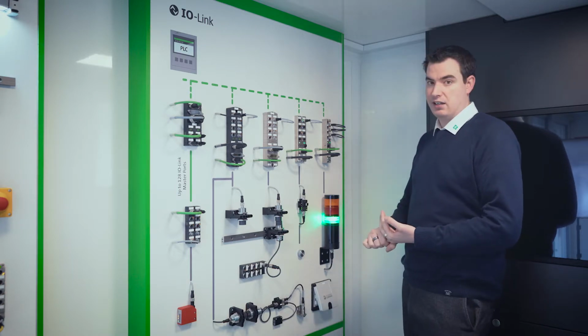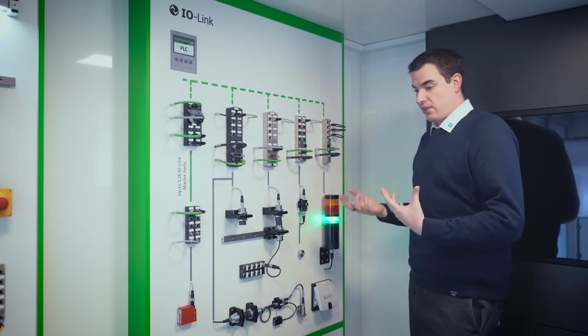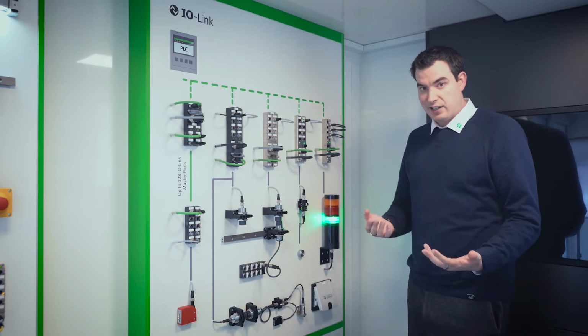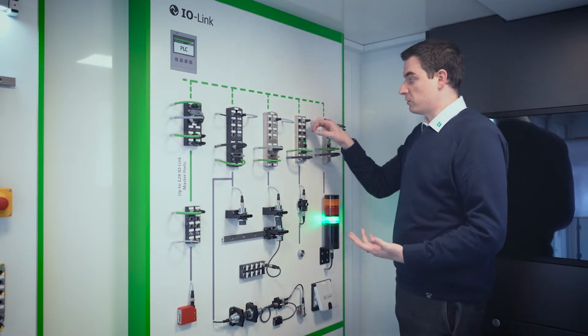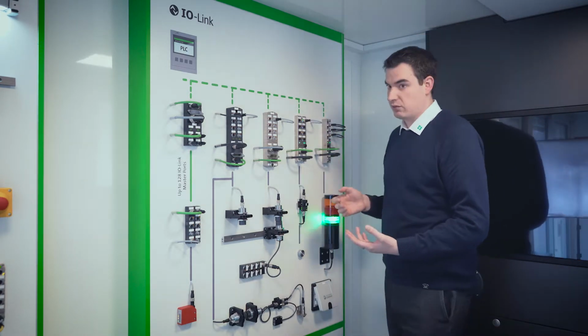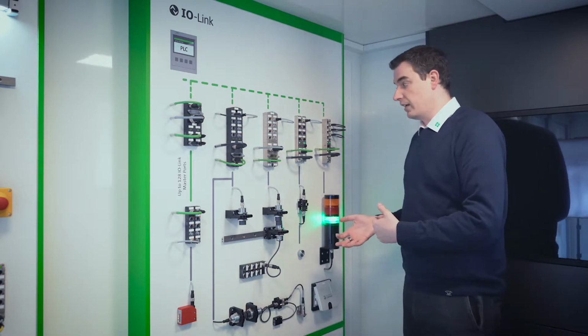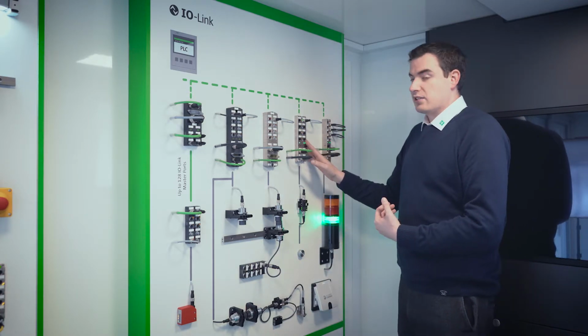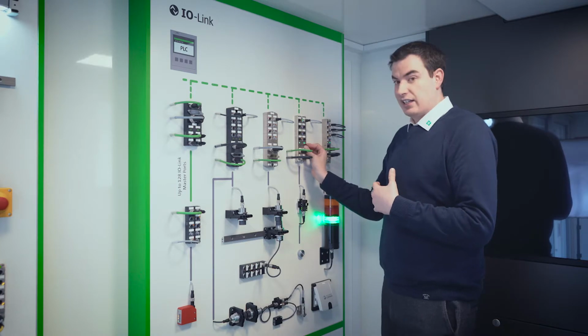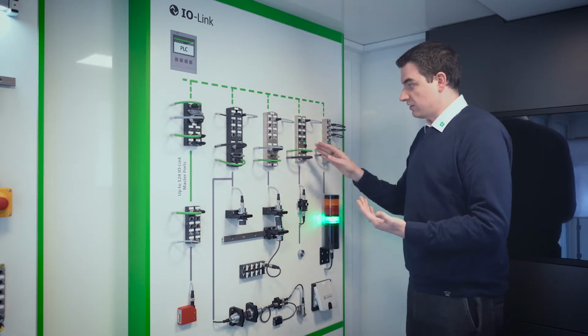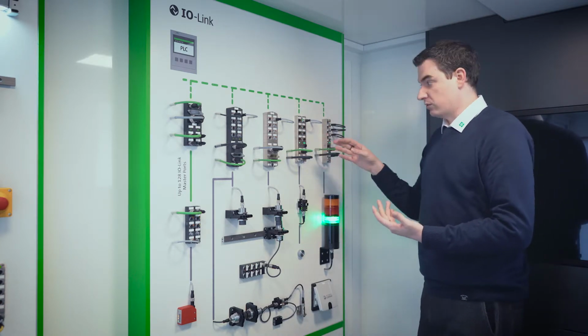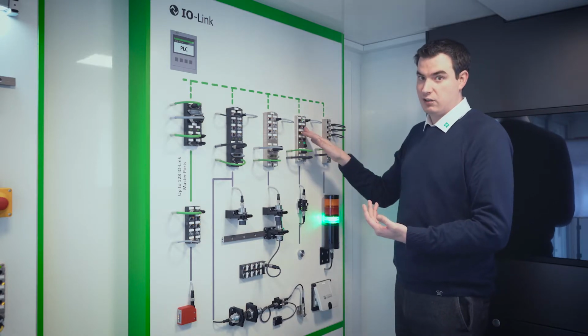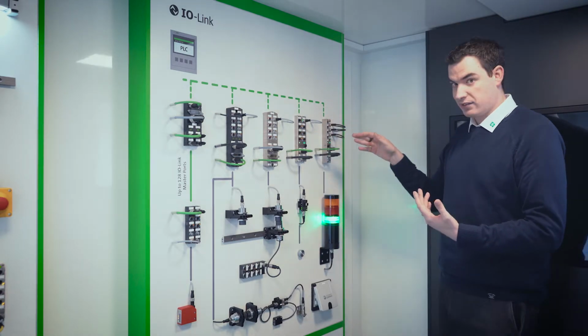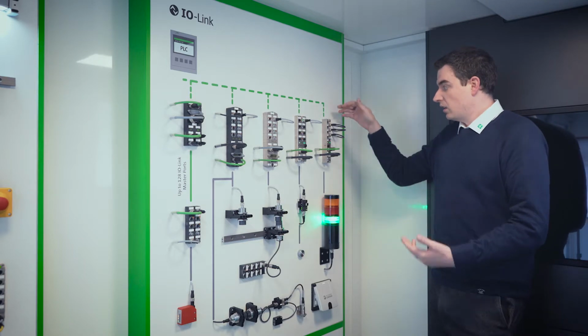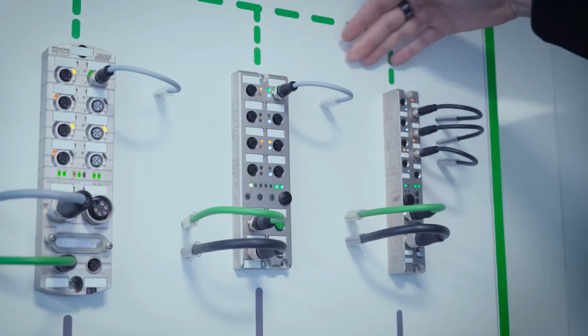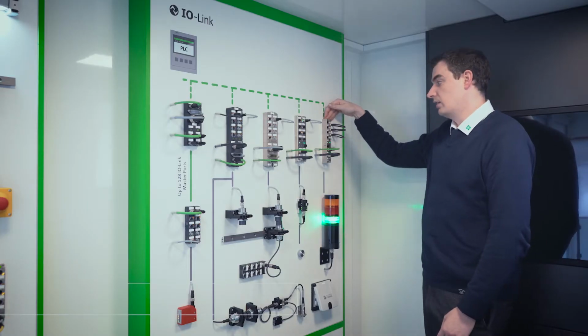the outputs and the IO Link, rather than waiting for the software engineer to get to site before they found that actually some of the points may have been wired incorrectly, or done to the wrong part in the software. Using the web server interface, the installation engineers on site can connect to this and view the actual data, not just see the LED coming on and off as they flagged the sensor. We have these in a 60mm or a 30mm range.